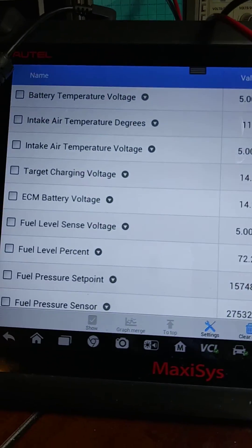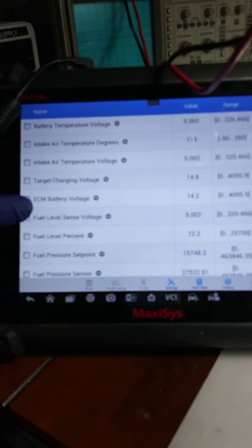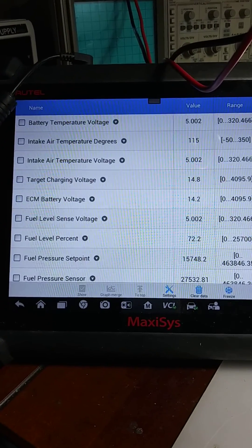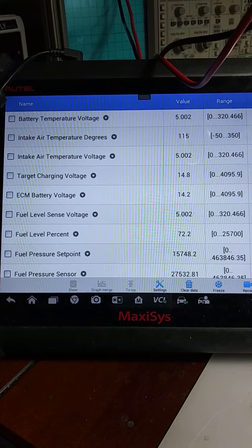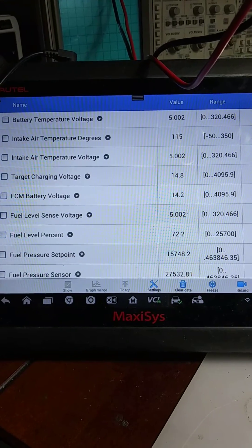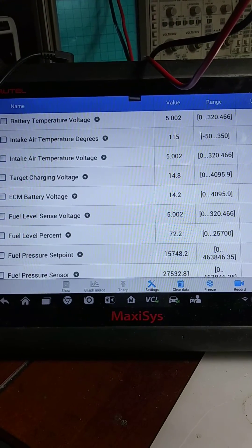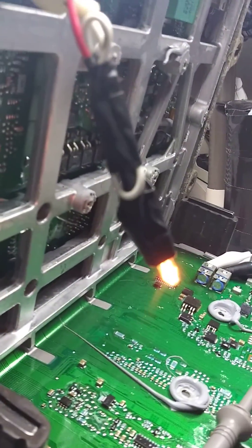If we look here, I have the live data pulled up and we can see our target voltage should be 14.8 for the charging. We are currently at 14.2, so that's why it is activated currently.